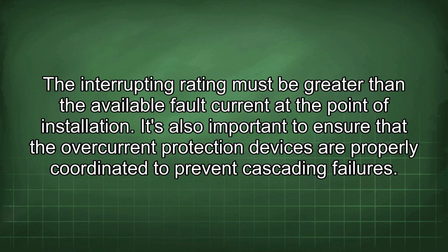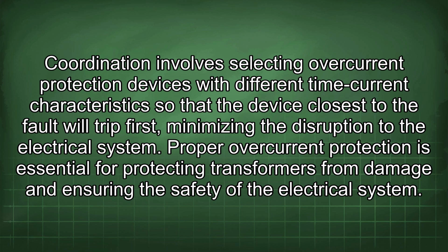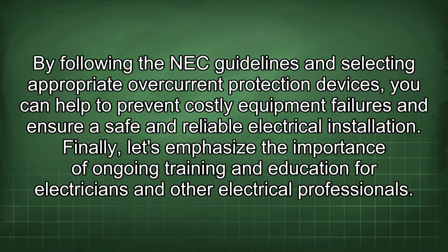It's also important to ensure that the overcurrent protection devices are properly coordinated to prevent cascading failures. Coordination involves selecting overcurrent protection devices with different time-current characteristics so that the device closest to the fault will trip first, minimizing the disruption to the electrical system. Proper overcurrent protection is essential for protecting transformers from damage and ensuring the safety of the electrical system. By following the NEC guidelines and selecting appropriate overcurrent protection devices, you can help to prevent costly equipment failures and ensure safe and reliable electrical installation.